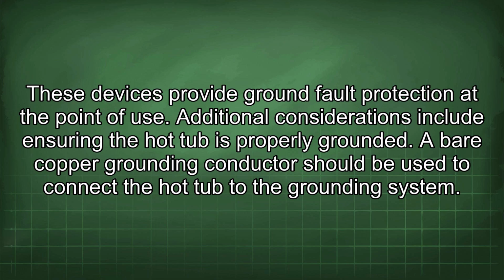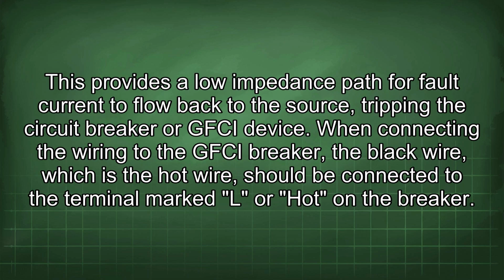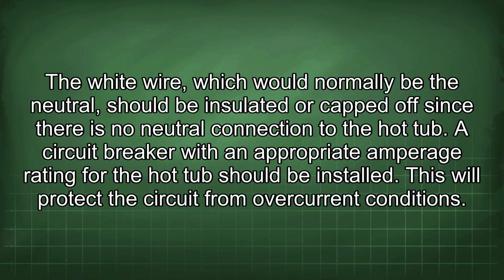Additional considerations include ensuring the hot tub is properly grounded. A bare copper grounding conductor should be used to connect the hot tub to the grounding system. This provides a lower impedance path for fault current to flow back to the source, tripping the circuit breaker or GFCI device. When connecting the wiring to the GFCI breaker, the black wire, which is the hot wire, should be connected to the terminal marked L or hot on the breaker. The white wire, which would normally be the neutral, should be insulated or capped off since there is no neutral connection to the hot tub.